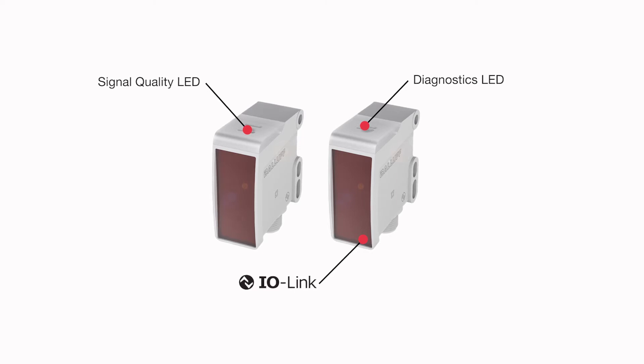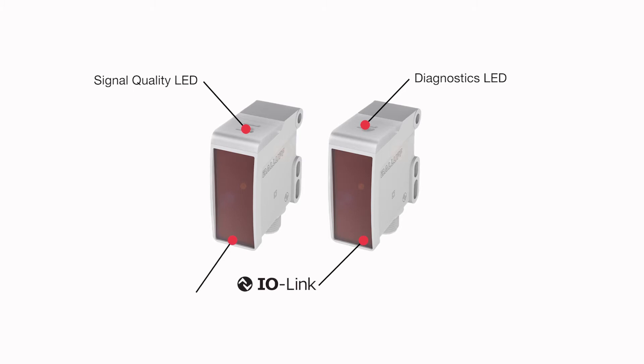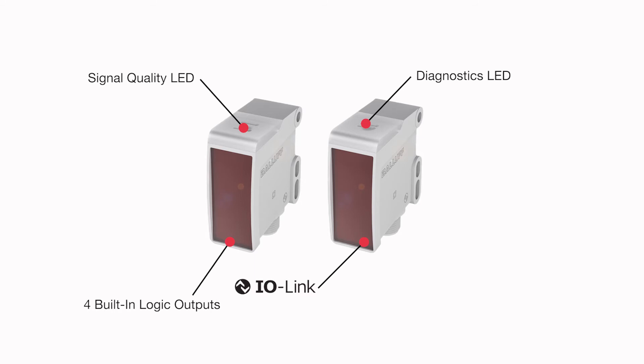The sensor's signal quality is displayed on an LED on the sensor, and operating hours and time functions are available using IO-Link. A second LED reveals diagnostic information. You can configure the functions on the connector pins as inputs or outputs, with digital outputs or even an analog output. You can also program up to four logic blocks, including using the output of a logic block as an input to another logic block. The sensors monitor signal quality and speed, and they include counters, sensors, and statistics as well.